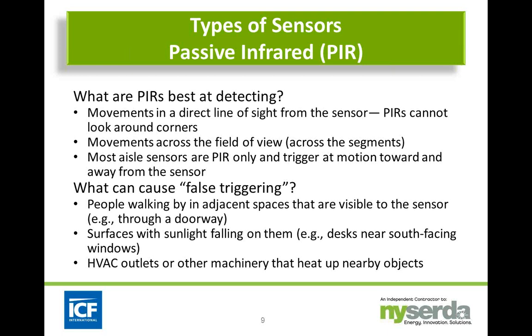Now, as I mentioned, these can either be a crossways motion across the sensor, which is the bulk of the devices for ceiling-mounted and wall-mounted sensors, but aisle sensors, which are designed specifically for warehouse storage-type aisle facilities, those are actually designed so that you can trigger motion by walking toward or away from the sensor. So you just have to make sure you know what kind of sensor you're working with.